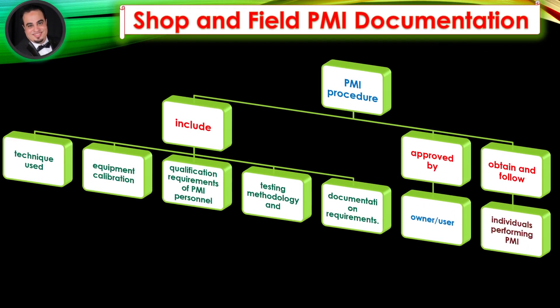Shop and Field PMI Documentation: A PMI procedure should include the technique used, equipment calibration, the qualification requirements of PMI personnel, the testing methodology, and documentation requirements. It must be approved by the owner/user, and individuals performing PMI should obtain and follow it.